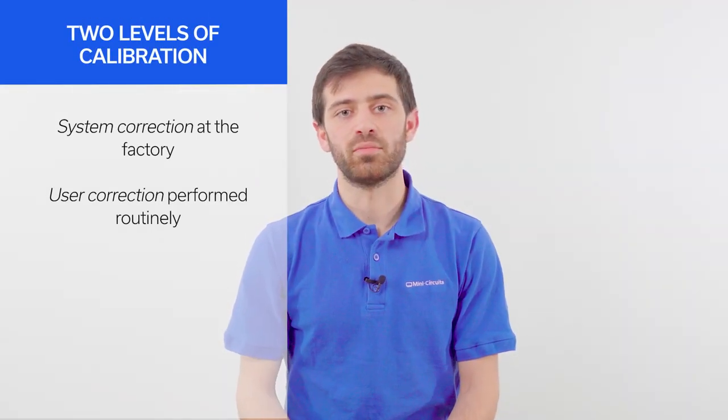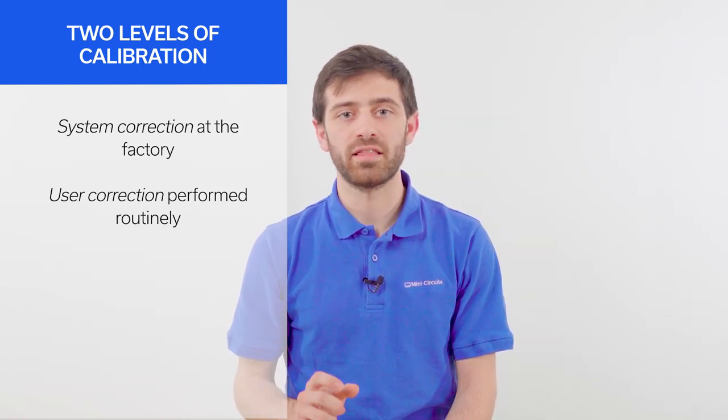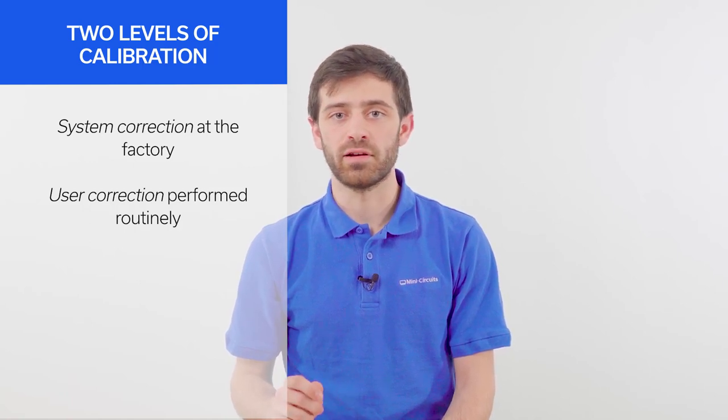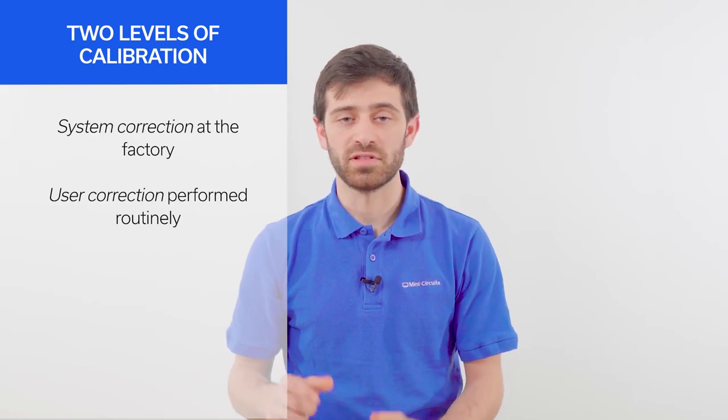Calibration is the process of acquiring the error terms that describe the systematic errors through measurements of known calibration standards. The eVNA has two levels of calibration. System correction is performed only once and done at the factory. User correction is done routinely by the operator to ensure accurate results, and that's what we're going to be walking you through today.